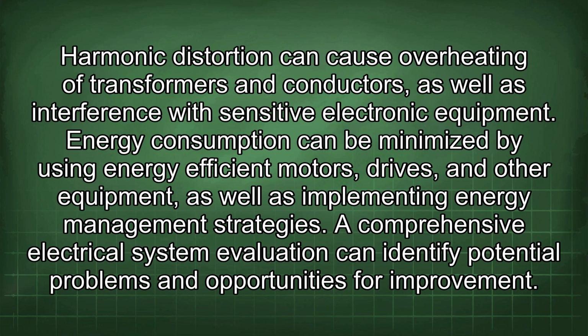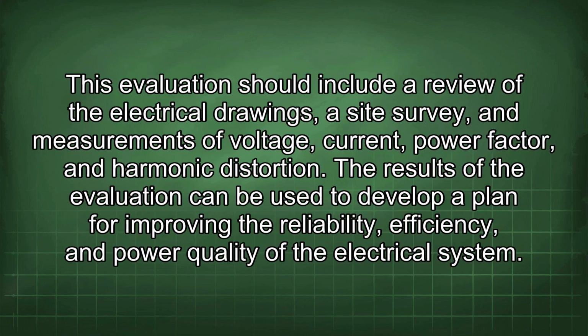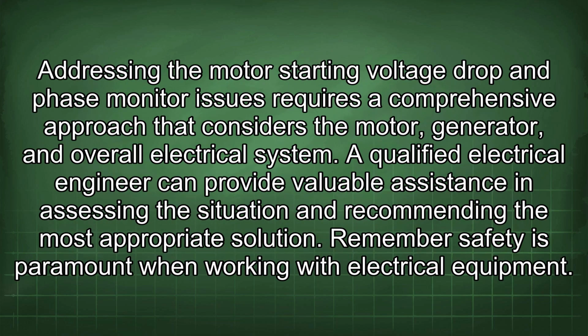A comprehensive electrical system evaluation can identify potential problems and opportunities for improvement. This evaluation should include a review of the electrical drawings, a site survey, and measurements of voltage, current, power factor, and harmonic distortion. The results of the evaluation can be used to develop a plan for improving the reliability, efficiency, and power quality of the electrical system. Addressing the motor starting voltage drop and phase monitor issues requires a comprehensive approach that considers the motor, generator, and overall electrical system. A qualified electrical engineer can provide valuable assistance in assessing the situation and recommending the most appropriate solution.